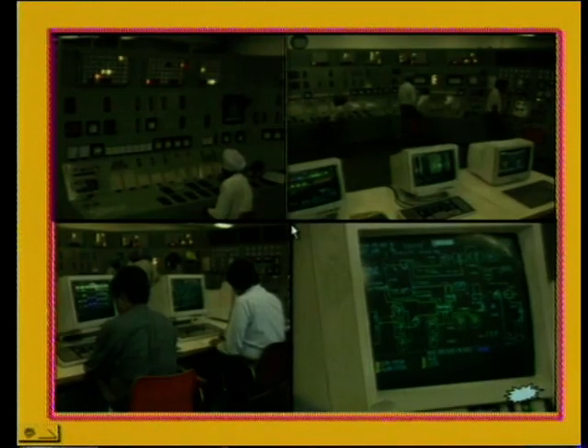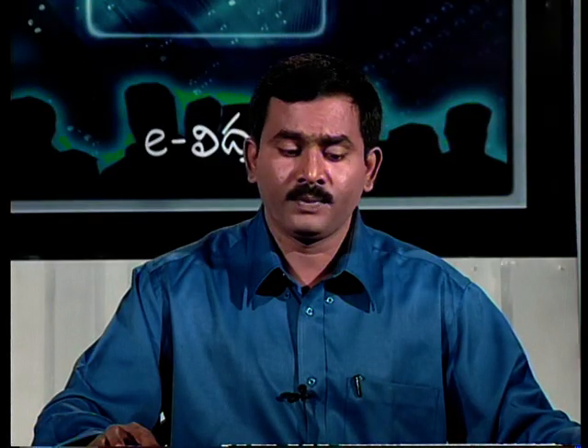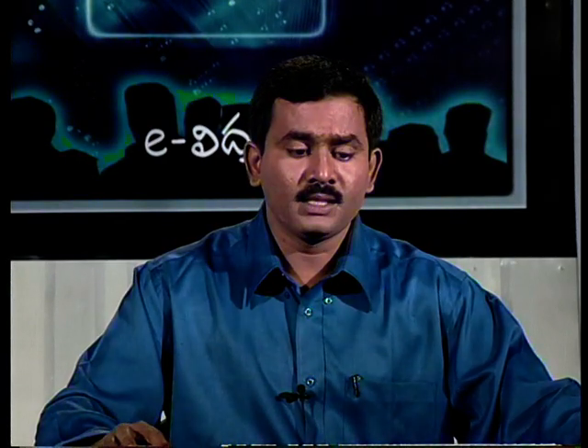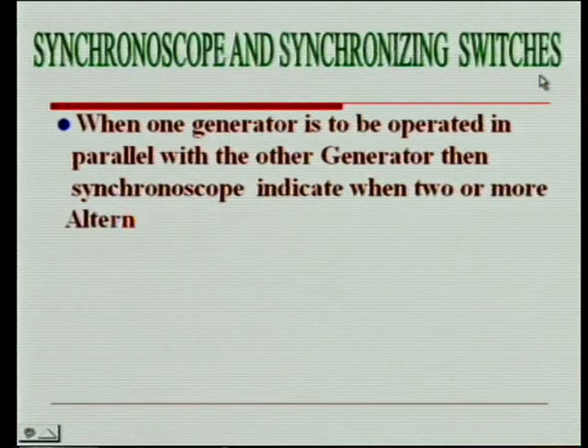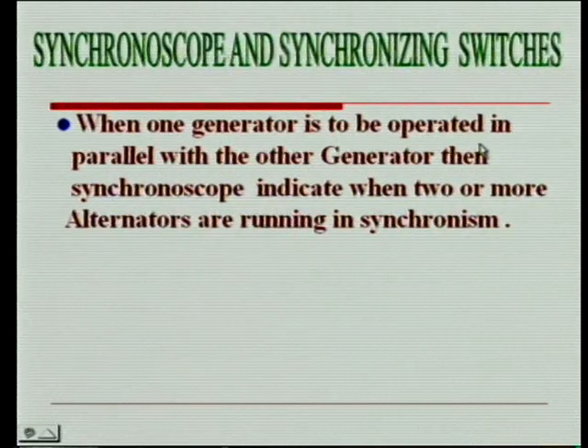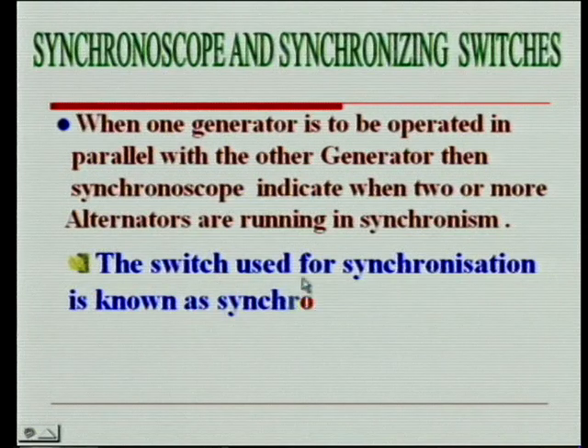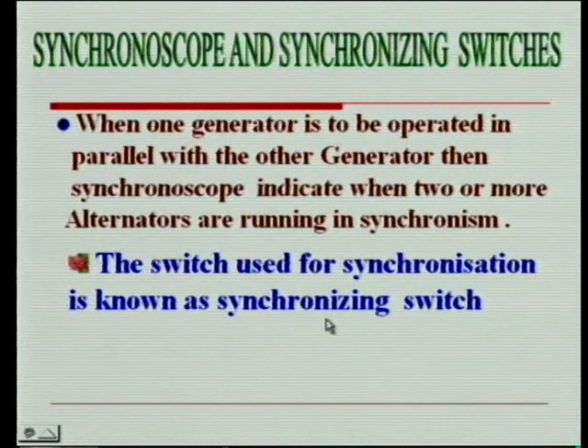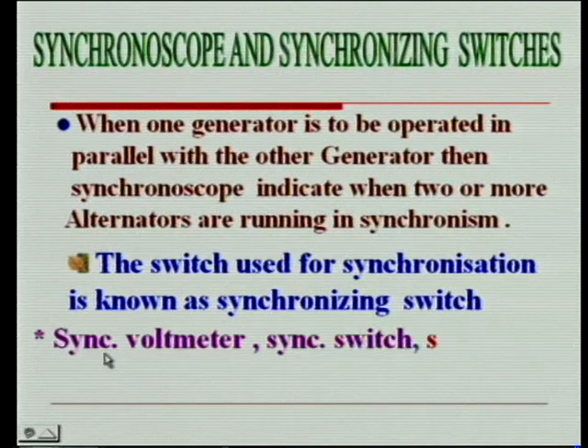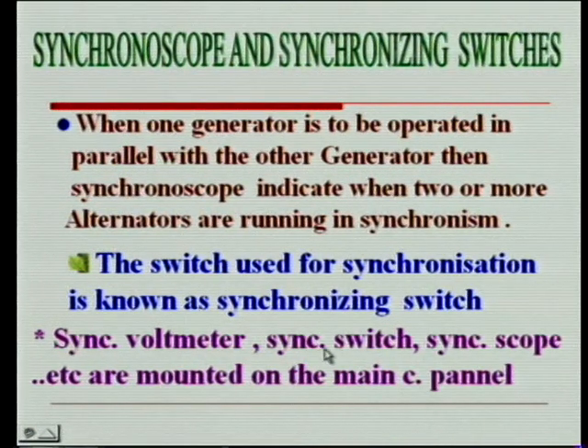I think you are now very familiar with the control room. Now, let us see what the main auxiliaries in the control room are. Here is a synchroscope and synchronizing switch. When one generator is to be operated in parallel with another generator, the synchroscope indicates when two or more alternators are running in synchronism. The switch used for synchronization is known as the synchronizing switch. Synchronizing voltmeter, synchronizing switch and synchroscope, etc. are mounted on the main control panel.